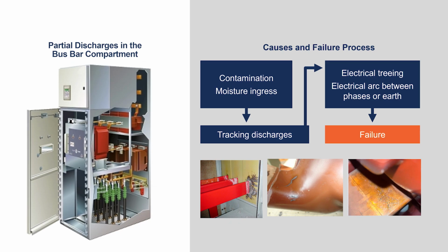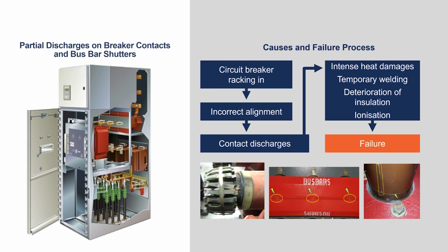And what is the biggest issue that you see? If you have a look at the switchgear itself, it's normally metal clad switchgear, 11, 22, 33, SF6 on the 132 kV side. But if you have a look at the components in the switchgear, you've got your breaker, your bus bar, your terminations, your cable, and your protection panel, which is looking after the protection side. But where do we, as Martech, find the most issues if we look at partial discharge and identifying defects in switchgear? So from a partial discharge point of view, James, we divide the switchgear into three sections.